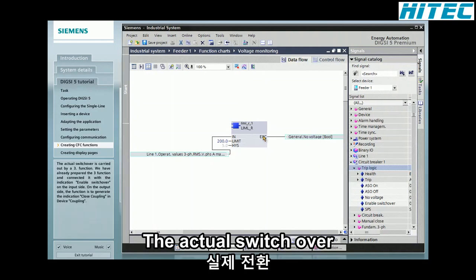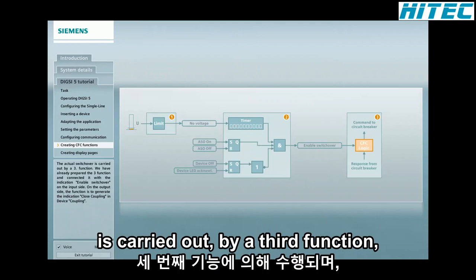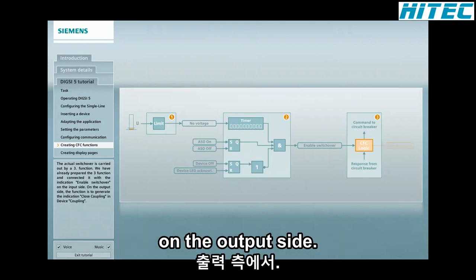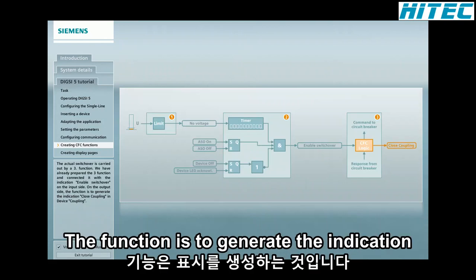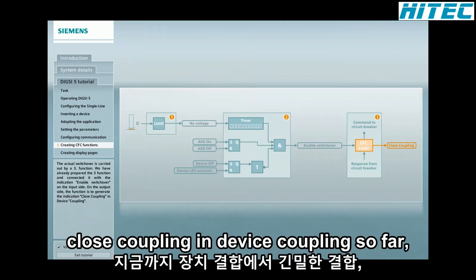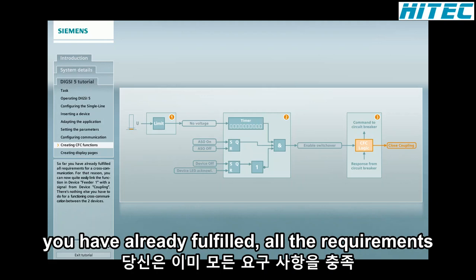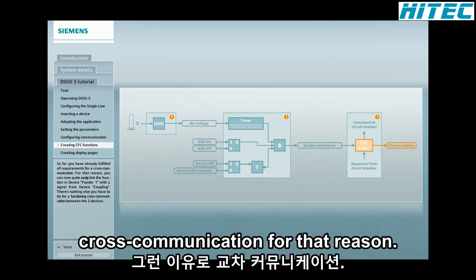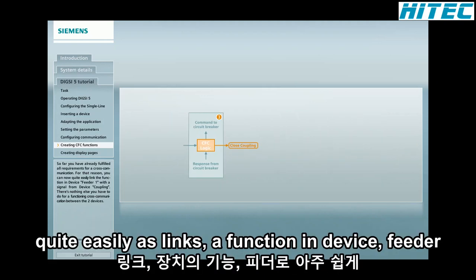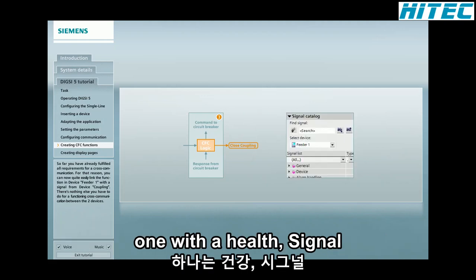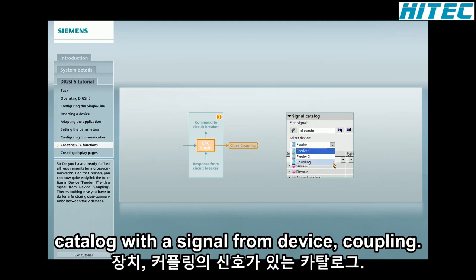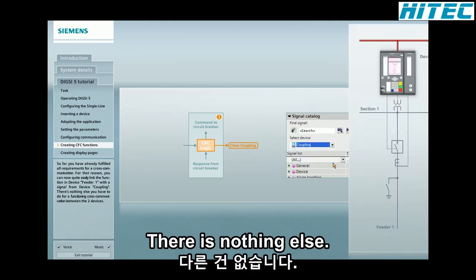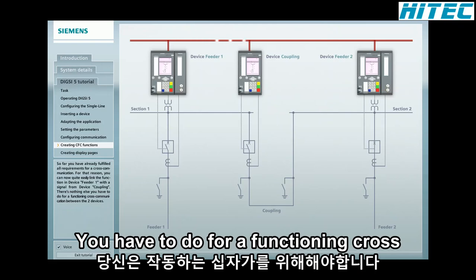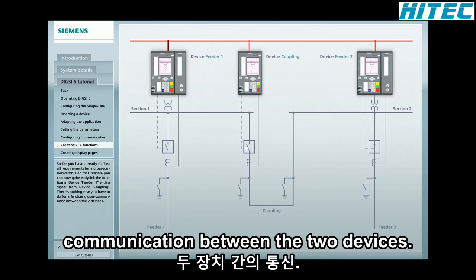The actual switchover is carried out by a third function. On the output side, the function is to generate the indication close coupling in device coupling. So far, you have already fulfilled all requirements for a cross communication. For that reason, you can now quite easily link the function in device feeder 1 with the help of the signal catalog with a signal from device coupling. There is nothing else you have to do for a functioning cross communication between the two devices.